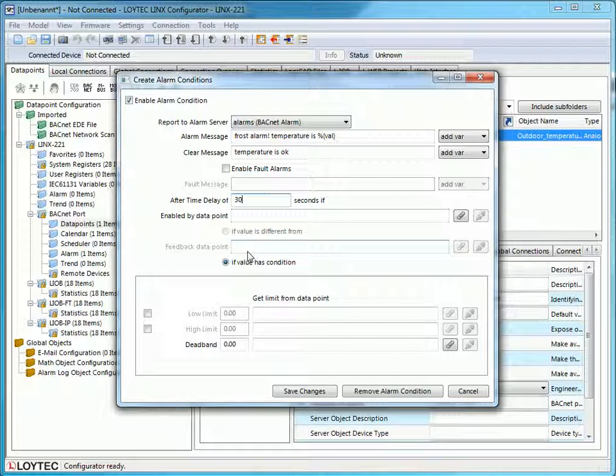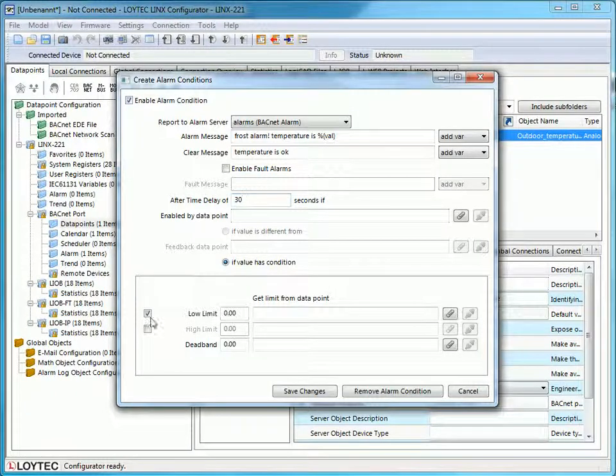Maybe if the alarm should be triggered by a temperature difference between two measuring points. In this example, we want to trigger an alarm when the outdoor temperature drops under 4 degrees Celsius. So we choose Low Limit 4 degrees.